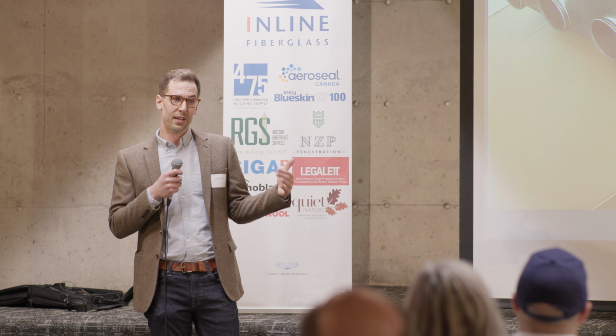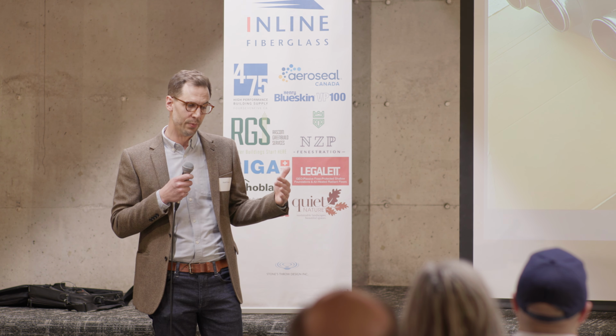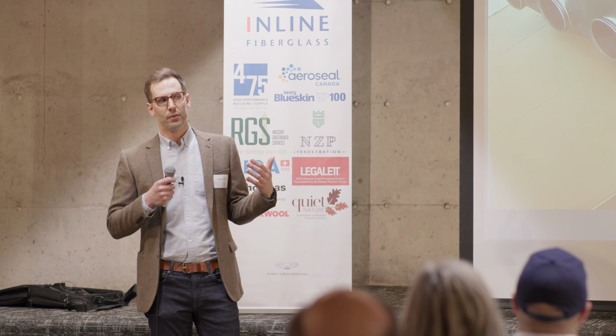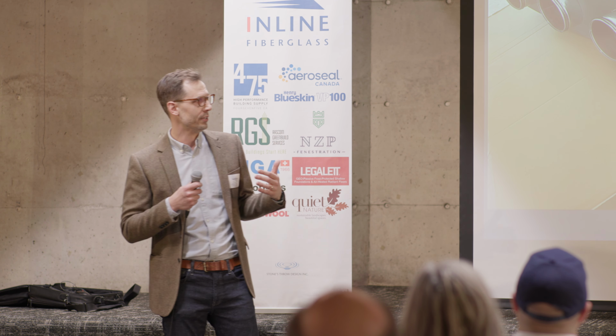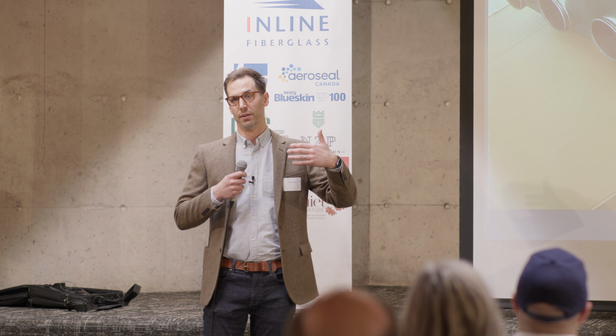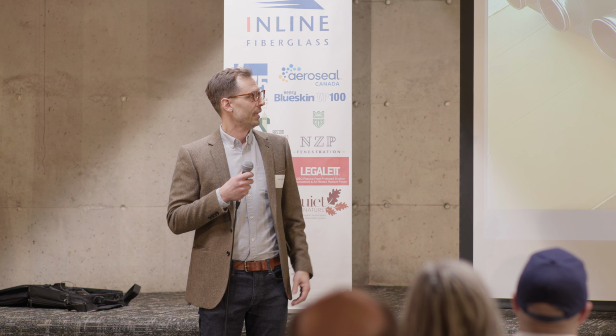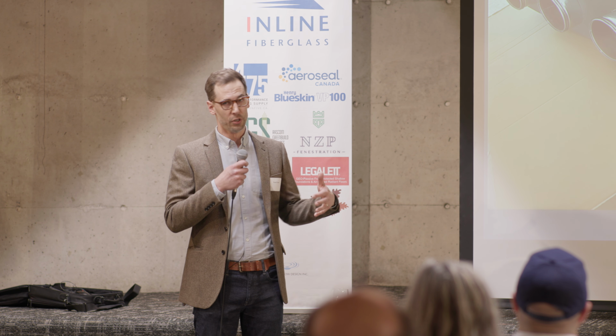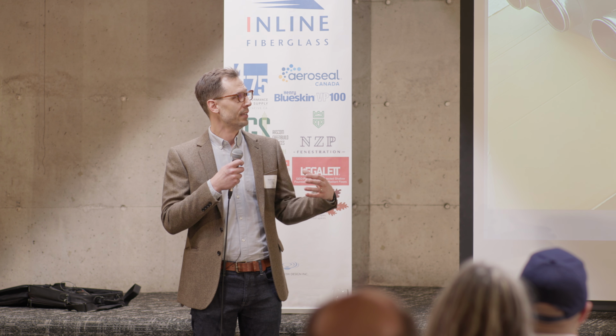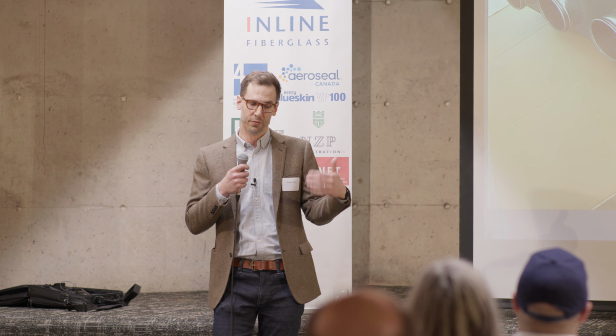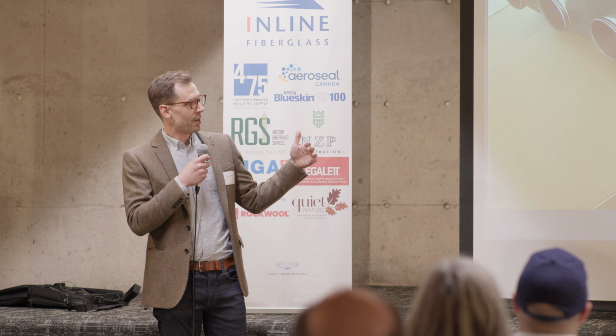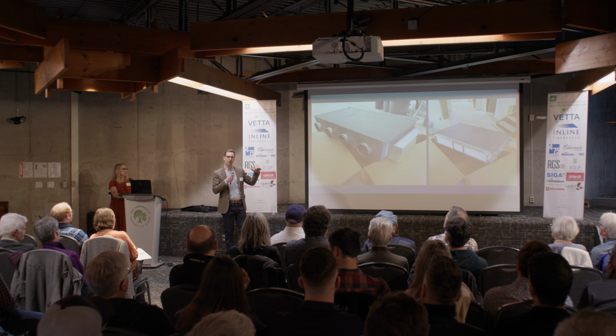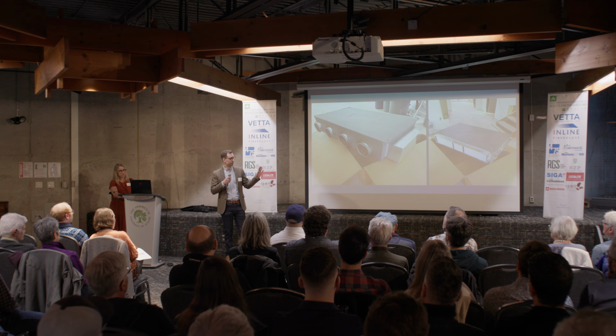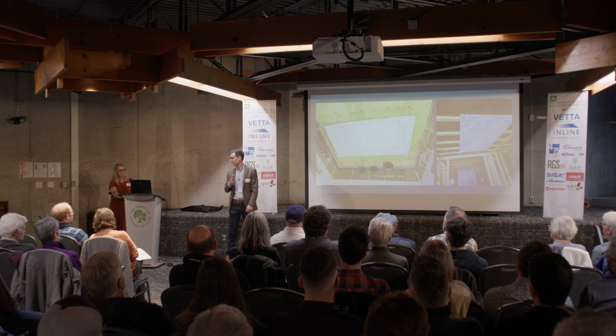You could do this by putting a fan coil in every single room, and lots of people have, but it's like, where do you want to do maintenance and how much maintenance do you want to do? Because then you're introducing a drain pan and a filter to change in all those rooms. If you go to a single air handler in the basement, you lose a lot of that zoning capability, but you've got the lowest maintenance. So this is kind of a hybrid in between where we've got 4 points of maintenance through the house, 4 fan coils, and I can live with that because of the level of control we're getting out of it.